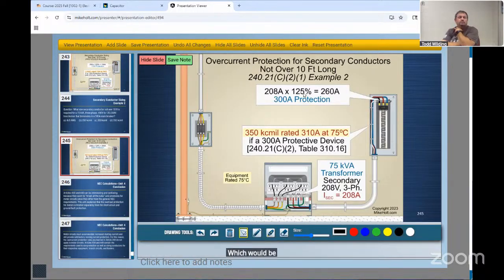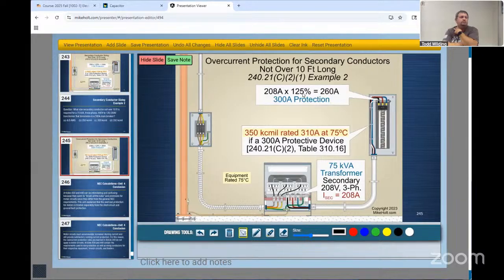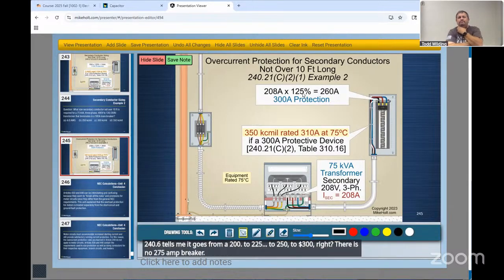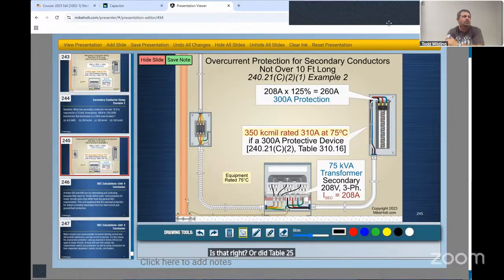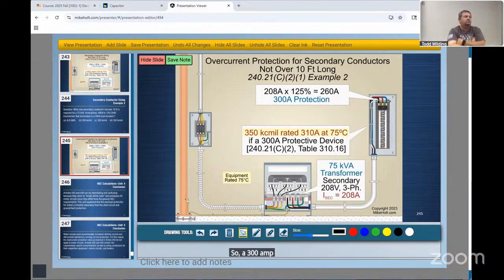Which would be what? 240.6. This is just copper wire. 240.6 tells me it goes from a 200 to 225 to 250 to 300, right? There is no 275 amp breaker. Is that right? Yes, it goes straight to 300. Okay, 250 to 300. So a 300 amp breaker is permissible.